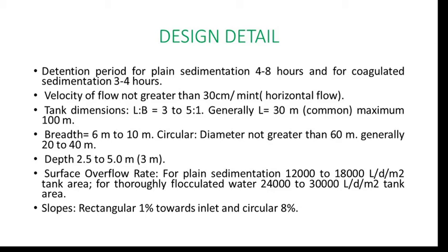So for a rectangular basin, the length to breadth ratio is considered as 3 to 5 is to 1. That means the length should be 3 meter or 5 meter and the breadth should be 1 meter. Generally the limiting length is 30 meter, or maximum it may be up to 100 meter, and the limiting width is up to 12 meter.